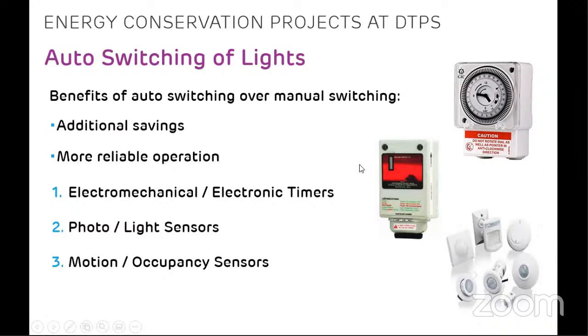The better advantage which we got from this was that sometimes in winter we have to switch on the lights earlier, or in summer we have to switch on lights later. So we don't have to go and change the timer setting. It will be taken care of by this photo sensor or light sensor automatically. Also, on rainy days, whenever it is very cloudy, even in afternoon hours, if the light intensity falls below the set limit, the lights will be switched on automatically, which is also a desirable feature of this photo sensor or light sensor. We haven't installed the latest technology yet, but we are soon progressing towards it. We can install motion or occupancy sensors.